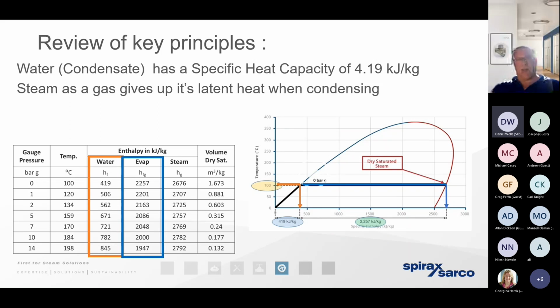The column next to the box in blue, marked steam, is the combination of the two previous columns, if you like. We call that the total heat. But of the total heat, the box in blue is the useful heat. And then after the steam has given up its useful heat energy to the process, to the heat exchanger, the energy that is left behind in the condensate is exactly the same as the energy that we added to the water to bring it up to boiling point.